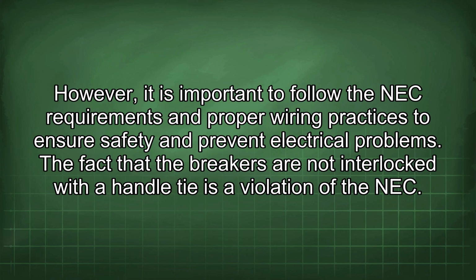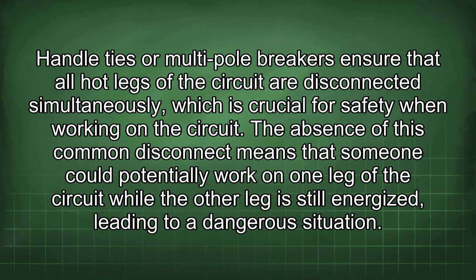The fact that the breakers are not interlocked with a handle tie is a violation of the NEC. Handle ties or multi-pole breakers ensure that all hot legs of the circuit are disconnected simultaneously, which is crucial for safety when working on the circuit. The absence of this common disconnect means that someone could potentially work on one leg of the circuit while the other leg is still energized, leading to a dangerous situation.